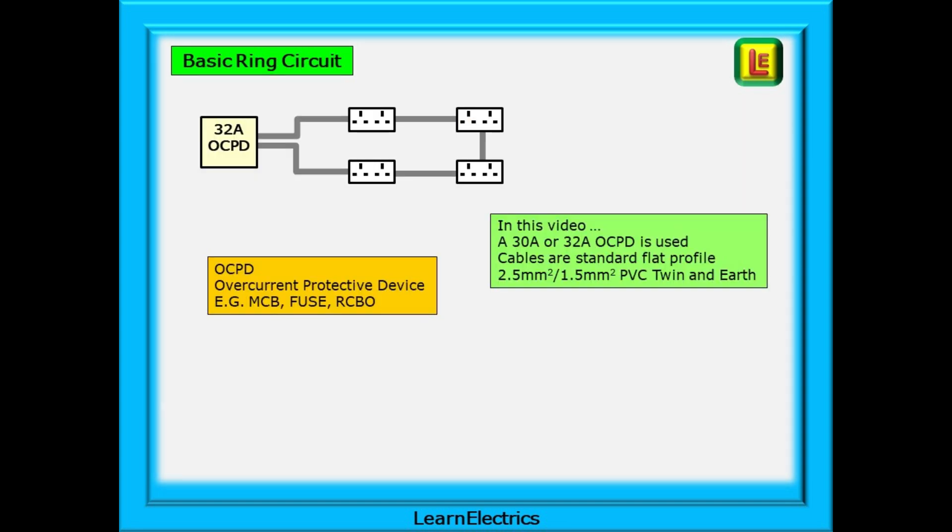This is our basic ring circuit. In this video we'll assume that a 30 amp or 32 amp OCPD is used. OCPD is an abbreviation for overcurrent protective device, in other words a circuit breaker or MCB, a fuse or an RCBO, but not an RCD. Cable sizes used in the video are relevant to the standard grey flat profile 2.5 by 1.5 PVC twin and earth, and we've assumed when needed that there are no adverse conditions or temperature issues that would require larger sized cables.